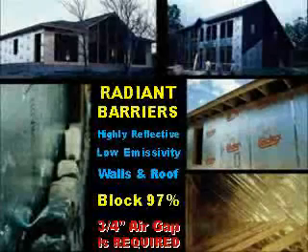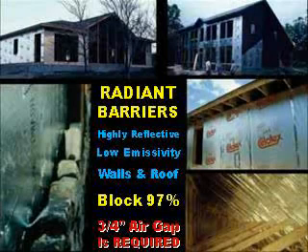Radiant barriers are nothing more than commonly available aluminum foil. You've been able to buy it in the grocery store for decades for around three cents a square foot — it's simply glued to construction materials. If you hold aluminum foil between your face and the bright summer sun, it reflects about 97% of the solar radiation. It also has very low emissivity, which means even if it gets hot, it does not radiate the energy into your home. In locations with air conditioning requirements, radiant barriers should be used on the roof and the walls. To be effective, it must have at least a three-quarter inch air gap that can convect any excess heat buildup away. Metal radiant barriers such as aluminum foil are highly conductive, so they must not touch adjacent materials on at least one side.